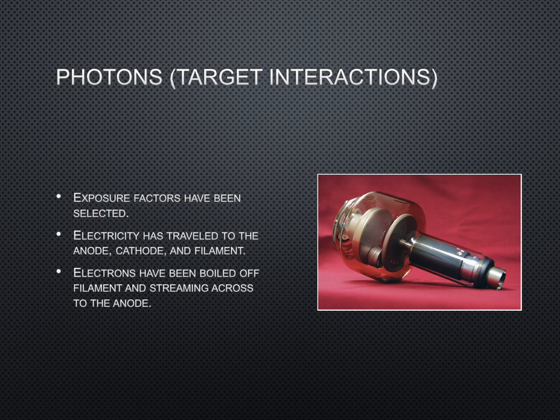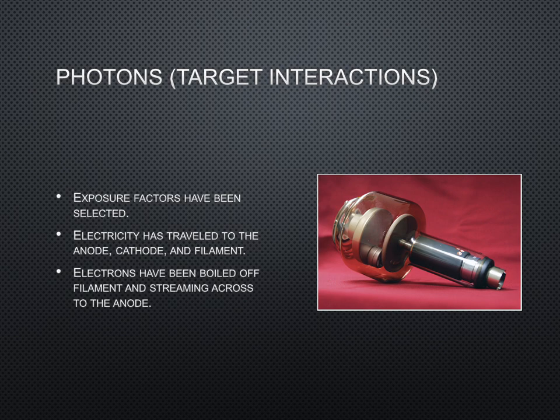The picture on this slide illustrates the inside of a general purpose x-ray tube. This may look familiar if you watched my video about the x-ray tube. Exposure factors have now been selected. Electricity has traveled to the anode, the cathode, and the filament. Electrons have been boiled off of the filament and are streaming across to the anode at tremendous speeds. The filament electrons penetrate the face of the target to a depth of approximately 0.5 millimeters and interact with the tungsten target atoms in their path.